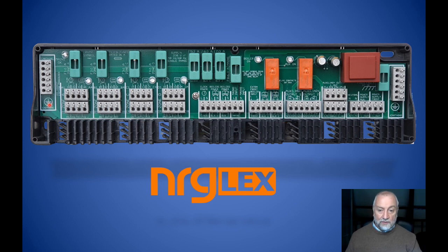The one thing I will say to you is the 4th terminal here at the top. So this is A. Again, if you remember our numbering back with the nrgZone, there was A, B, C and D. This is electrically Zone A, Zone B, Zone C, Zone D. So I would strongly suggest that if you were using the energy lex with the nrgZone, that you keep A's together and B's together and whatever. So if you're looking at the 3rd pump, it should be wired from the 3rd fuse and the 3rd circuit here.